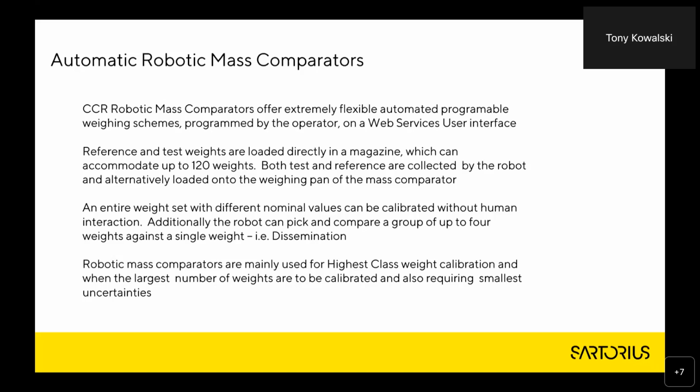But mostly class E and class F1 are the weights that are usually calibrated on either robotic or carousel type mass comparators.